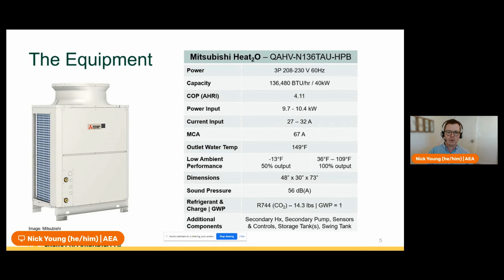This product has a lot of advantages. First of all, low GWP. You really can't beat CO2 for GWP. CO2 also has really great low ambient performance, really the best of any refrigerant being used in current heat pump water heaters. It maintains output and efficiency well below freezing. You can see in the chart in the upper right, you've got full heating capacity even at 36 degrees Fahrenheit, or 2 degrees Celsius, and you maintain 50% of your heating capacity all the way down to minus 13 degrees Fahrenheit. Really fantastic low ambient performance, which basically makes it a no-brainer in California, especially coastal California, where we're barely even going to hit freezing.